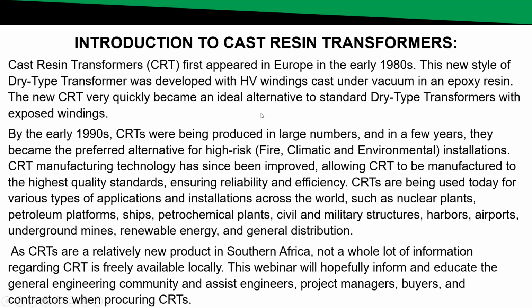Cast resin transformers appeared early in the 1980s in Europe. This new style of cast resin transformers was developed with HV windings cast under vacuum in epoxy resin. The new cast resin transformer very quickly became an ideal alternative to standard dry type transformers with exposed windings. In the early 1990s, cast resin transformers were manufactured in large quantities, and they became the preferred alternative for high-risk installations.